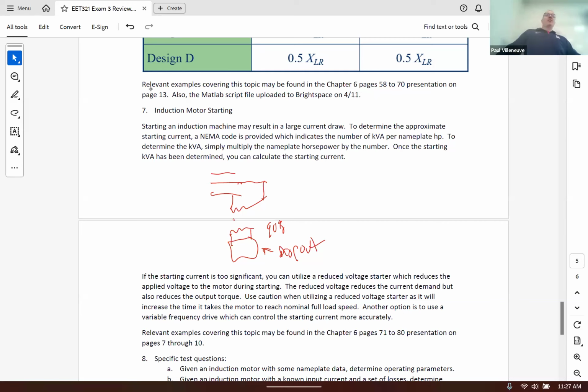You can buy a transformer that has a lower impedance. Is that okay? Maybe. The problem is whenever you have a fault on the low side of that transformer, you're going to get boatloads more fault current, which could potentially mean your system gets more damage. Or you can just say, I'm just going to buy a low voltage starter, start the motor, and then once it gets close to running speed, switch on to that speed. As long as I'm allowed to run for a period of time and I won't damage the mechanical system, that's by far the preferred way.